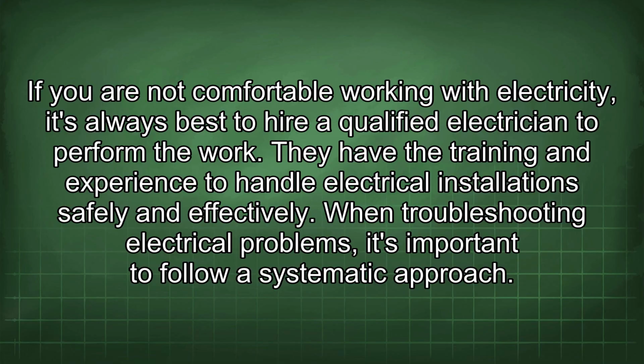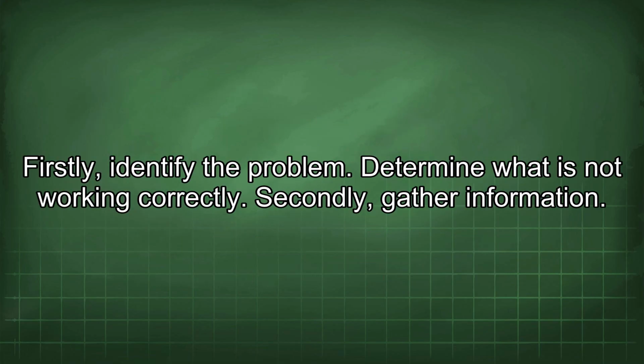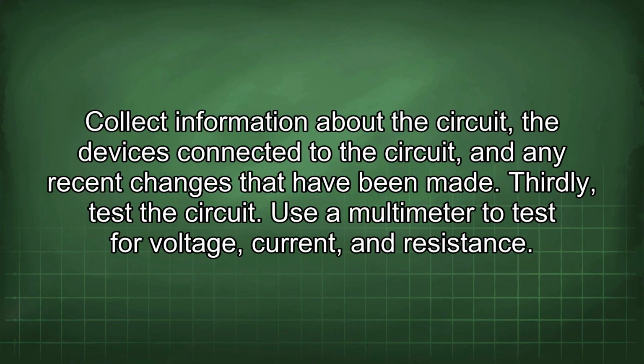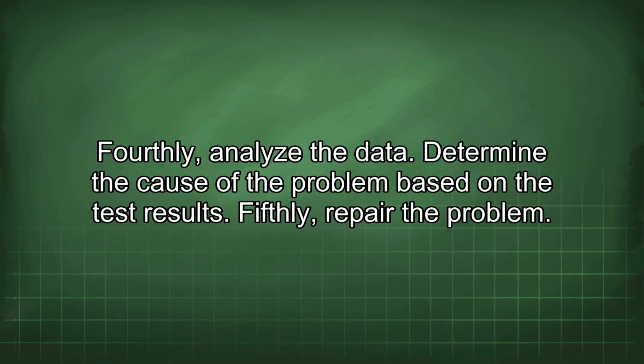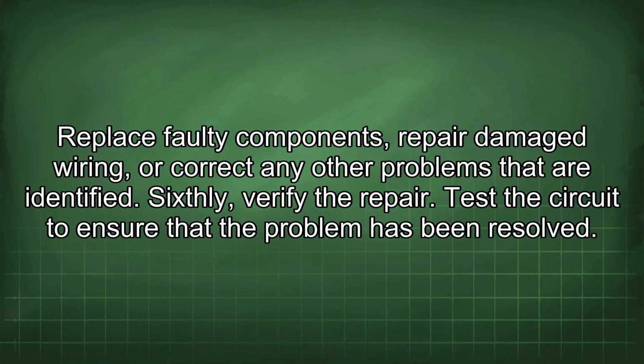When troubleshooting electrical problems, it's important to follow a systematic approach. Firstly, identify the problem. Determine what is not working correctly. Secondly, gather information. Collect information about the circuit, the devices connected to the circuit, and any recent changes that have been made. Thirdly, test the circuit. Use a multimeter to test for voltage, current, and resistance. Fourthly, analyze the data. Determine the cause of the problem based on the test results. Fifthly, repair the problem. Replace faulty components, repair damaged wiring, or correct any other problems that are identified. Sixthly, verify the repair. Test the circuit to ensure that the problem has been resolved.